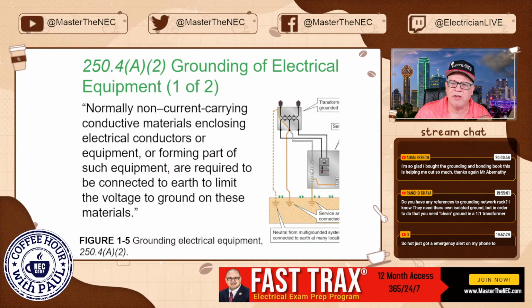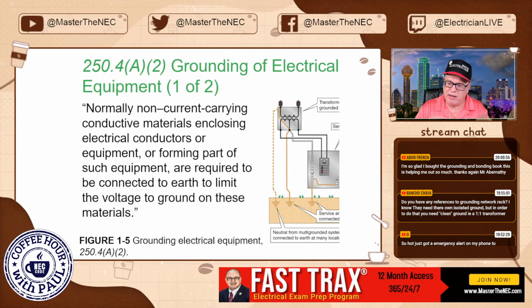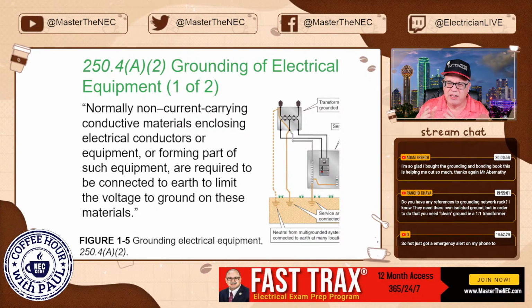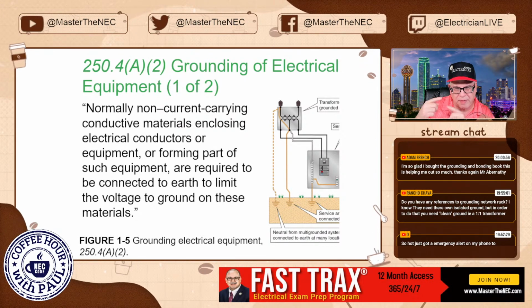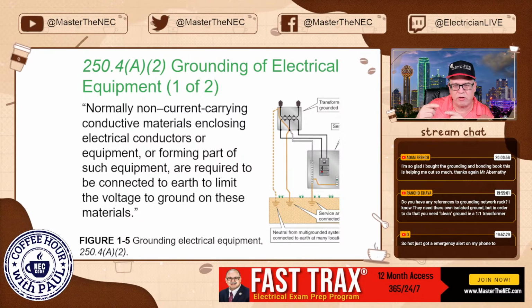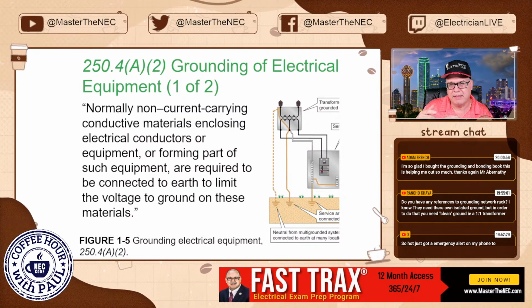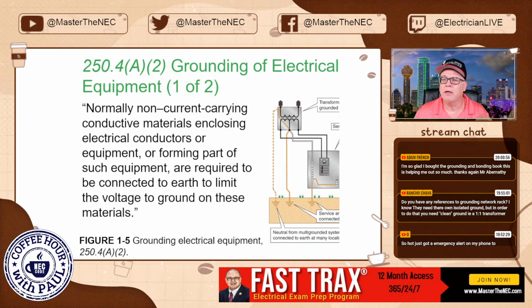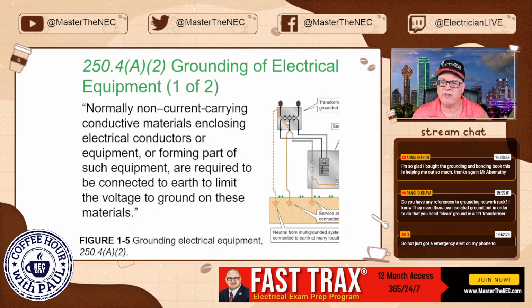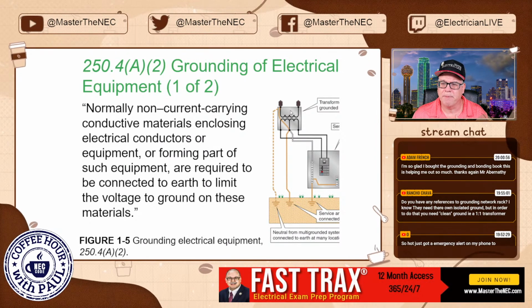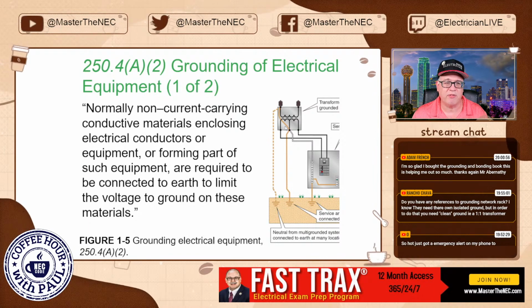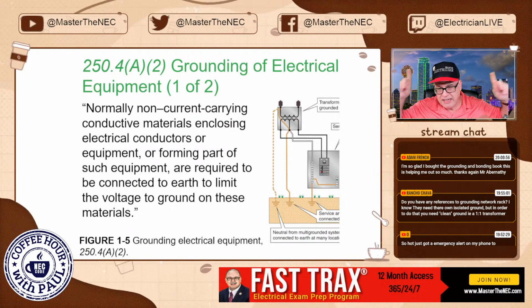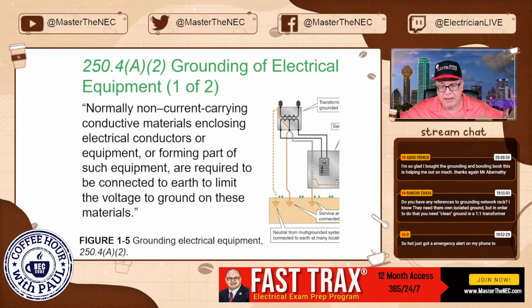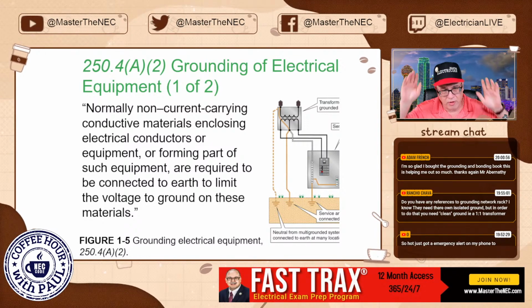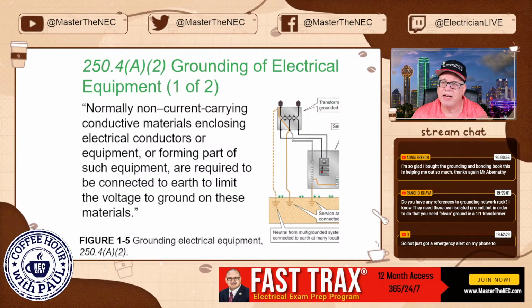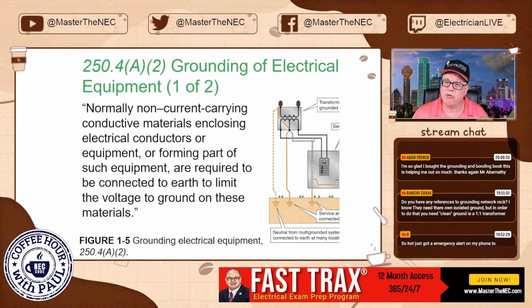Just being careful here, because I want to show you something. This right here, now this is where a lot of people say, well, wait a minute. You mean I can connect this neutral on the supply side to the metal enclosures and everything upstream? Absolutely. Code allows for it. But here's your transformer. And let's say this is a utility transformer, okay, which they're going to use what's called a multi-grounded system, meaning every so many feet, like 200 feet or whatever it may be, they're going to be making their connection to earth along the transformer setup. And here it's dropping down to your house, okay?